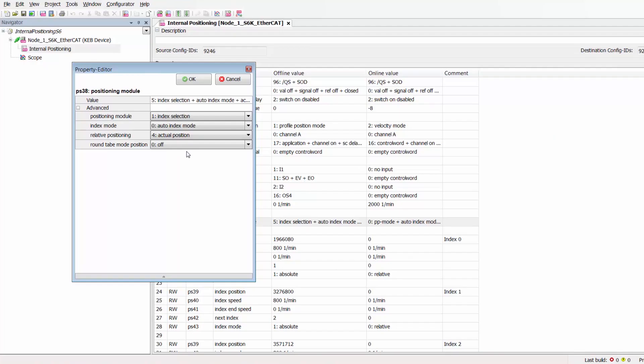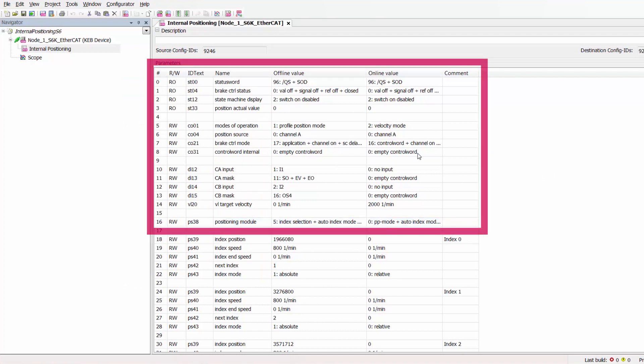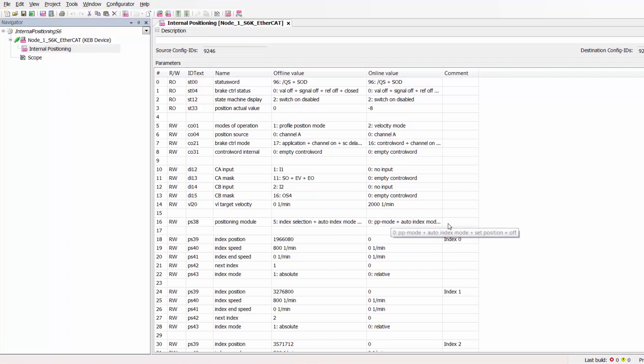So exit out of the positioning module dialog box and the parameters that we have discussed thus far in this parameter list represent the formation of the shell of the internal positioning module in the S6 drive. We have set our profile positioning mode, we have set our positioning source to the encoder, we have configured our control word to be controlled via digital input, we have set our positioning module for index selection and now the only thing left to do is to program our actual indexing positions.